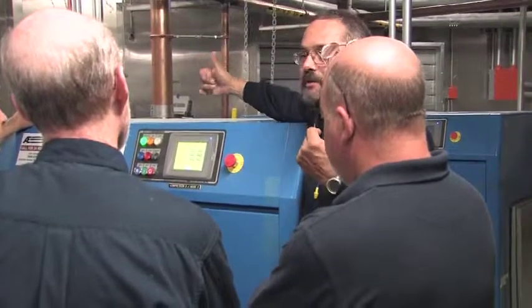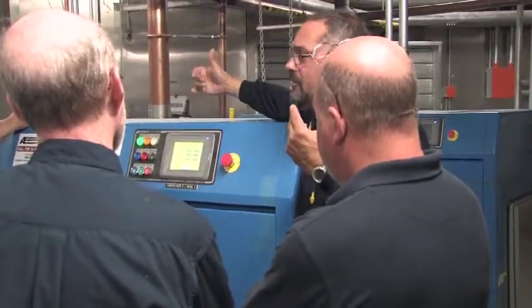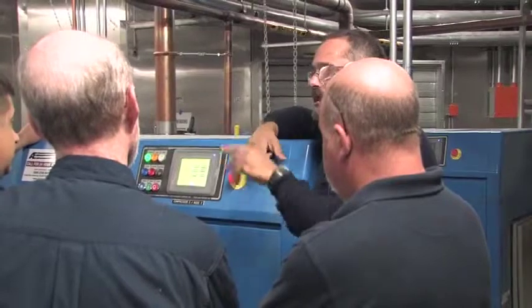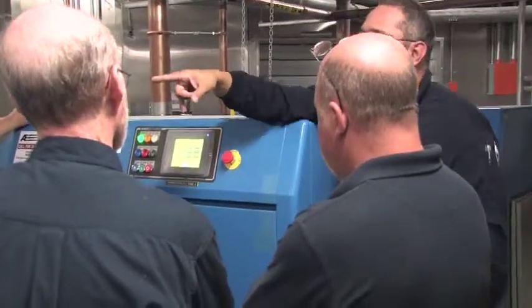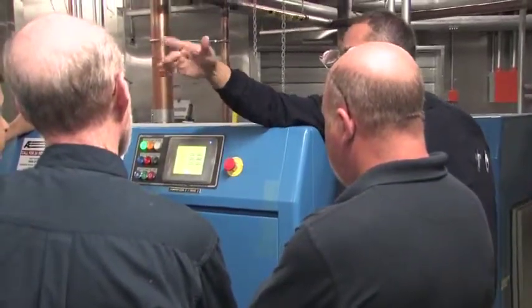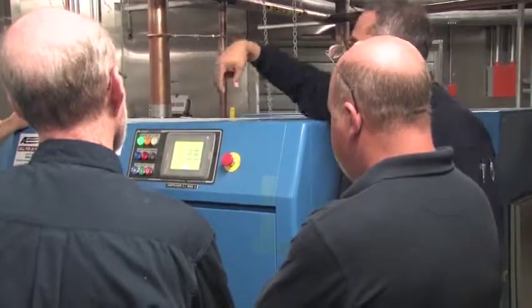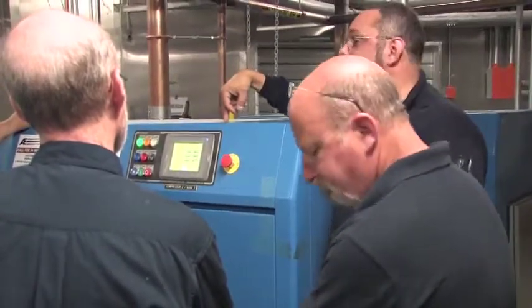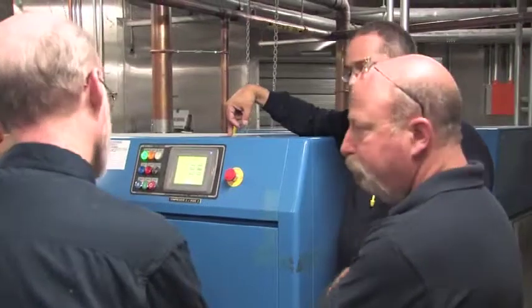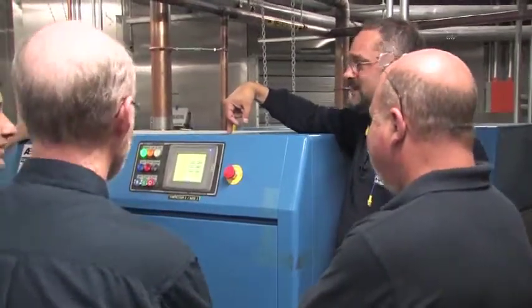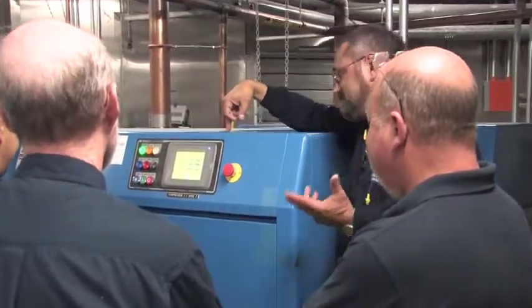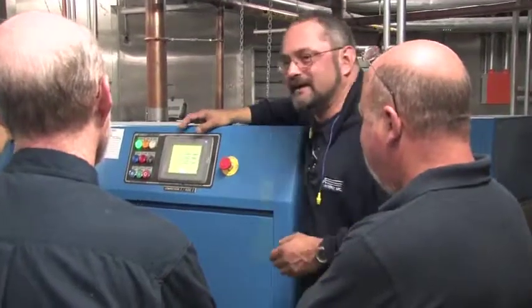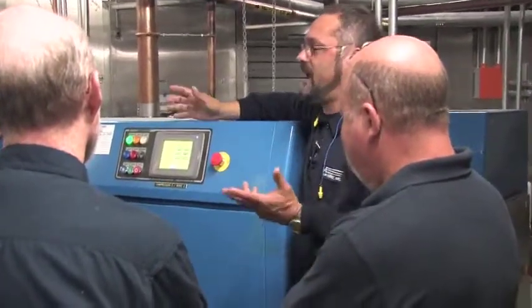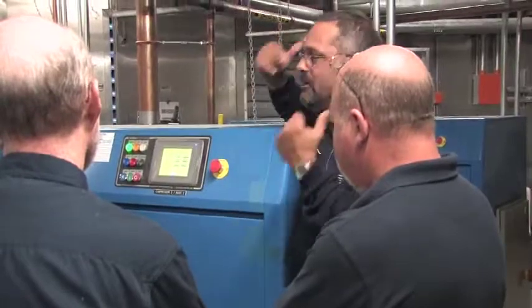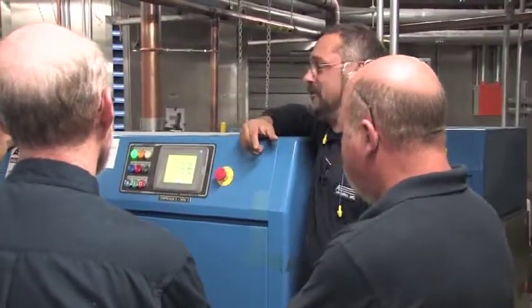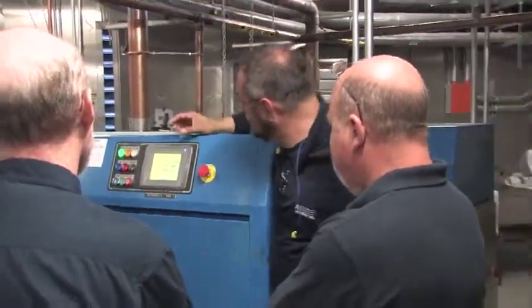So of course you get somebody saying my lag alarm's going off. Well, yeah, it is, because at noontime, or what it thinks is noontime, this machine which was in the lead is now switching to lag. This one was in the lag, but it thinks it's only 10 o'clock. So I'm still on break for 2 hours. It's not switching for another 2. Not my turn yet. So of course what happens is they're both in lag. They both trigger. What does the lag alarm do? It goes on. Hey, you've got problems here. It's time.